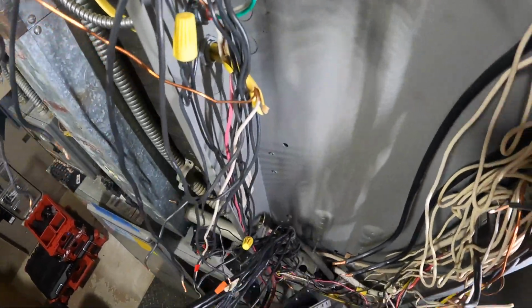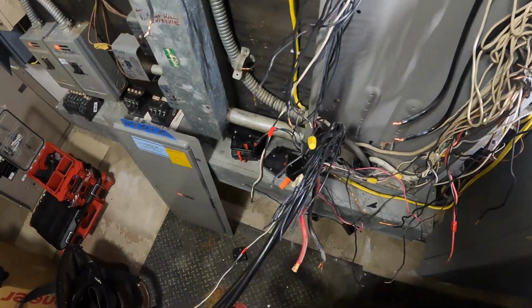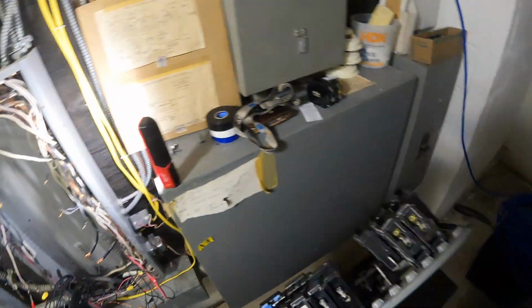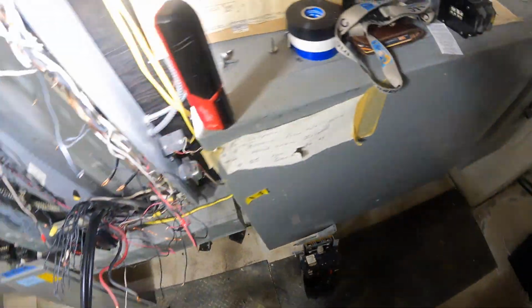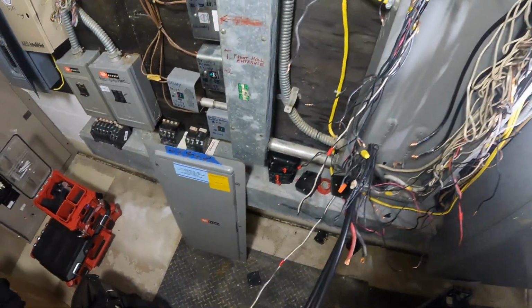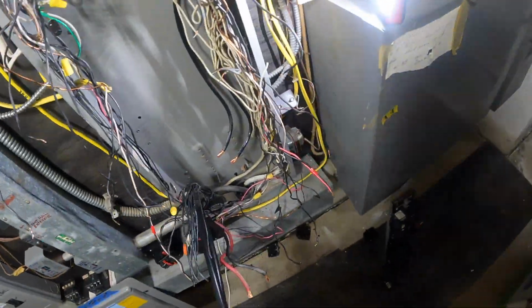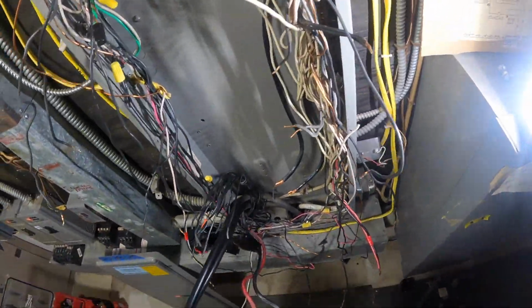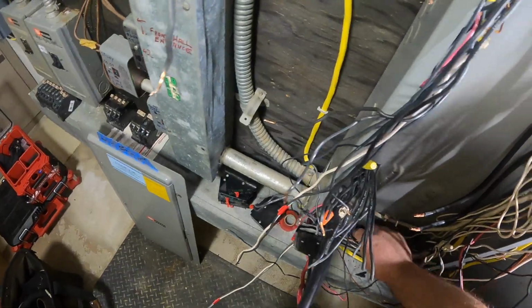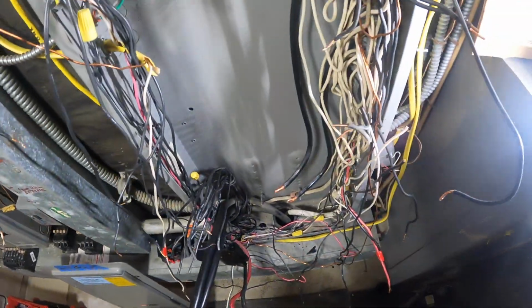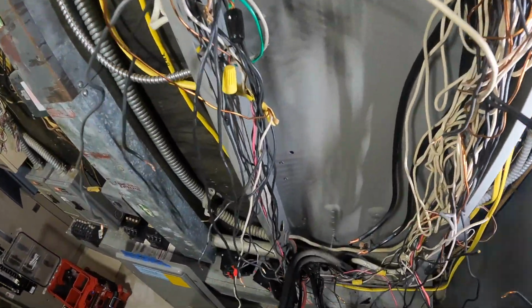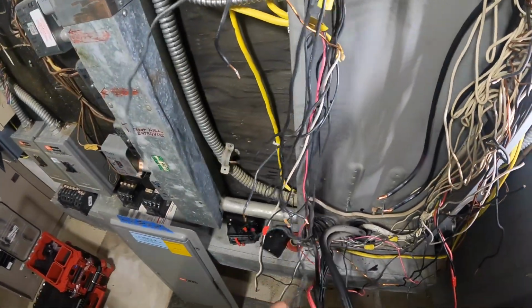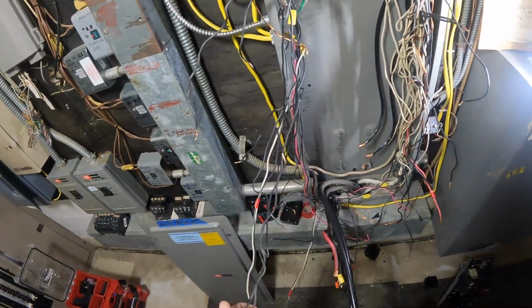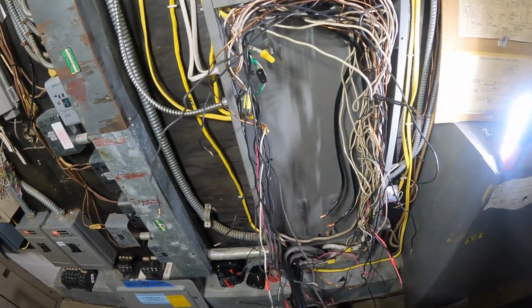And then, of course, I'll cut the ungrounded conductors when I get a moment here. And as you can see on the bottom, there's a wiring trough, which is where this wiring goes through, and it feeds a couple other things here. I didn't get too involved in any of it. I was just there to change this one panel, and I just reused these service entrance conductors, or rather, these are feeders at this point. Once you leave that main breaker, downstream from there, everything feeding other panels will be known as feeders. That's how it's defined by the NEC anyway.